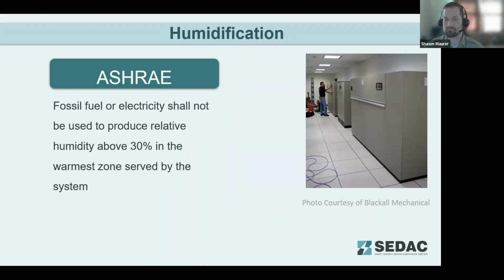In winter, relative humidity is generally fairly low, so we're going to spend a lot of energy to add that back into buildings. Humidifiers typically require substantial quantities of energy to provide that humidity, so limiting the amount of that energy is a needed requirement. So ASHRAE is limiting that relative humidity to 30% in the winter time, so we're not overly humidifying our buildings.